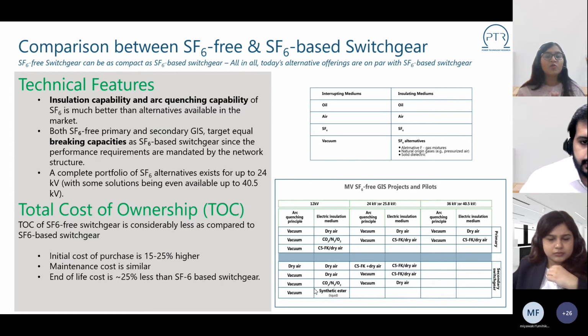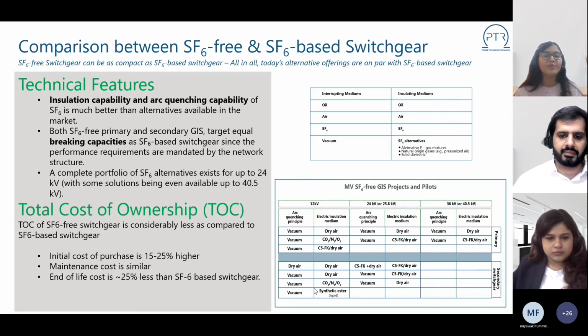Moving on, if we discuss the total cost of ownership of SF6-free switchgear and SF6-based switchgear, it is very important to consider the initial cost of purchase. It is 15 to 25% higher than SF6-based switchgear, which is extremely high in terms of amount, and in some cases it could even increase to 30%. However, from the market perspective, as the demand increases, the price would go down, and the initial cost of purchase would come within acceptable limits.